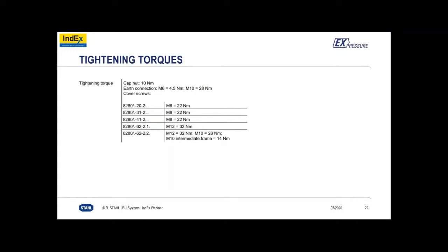Yep. So as with a typical EXD, we have specified torque ratings, so the use of a torque wrench obviously is required. This is a typical fault within hazardous areas where EPCs, end users, and inspectors are not using a torque wrench. I would figure for an enclosure, that would be very important. If anybody's watched our webinar number 6, missing one bolt or loose bolts will allow arcs, sparks, and overpressure to escape the box at a pressure that it's not designed for. So same thing for the ExPressure enclosure. They need to be torqued as per the IOMs and the certificate.